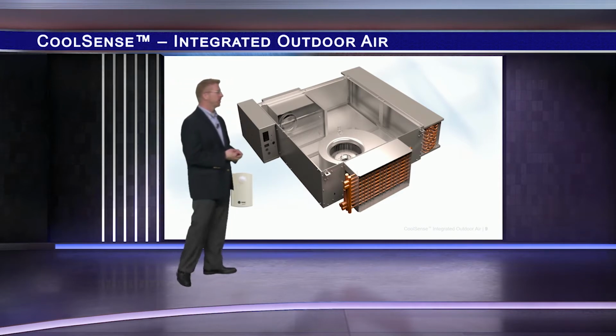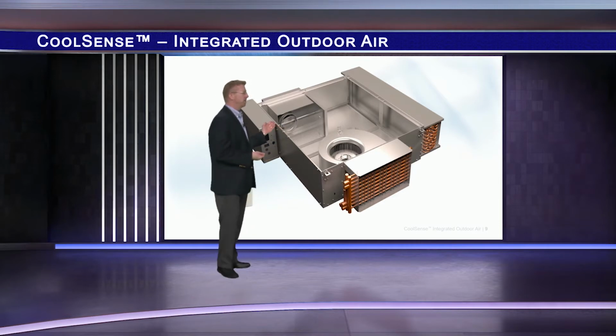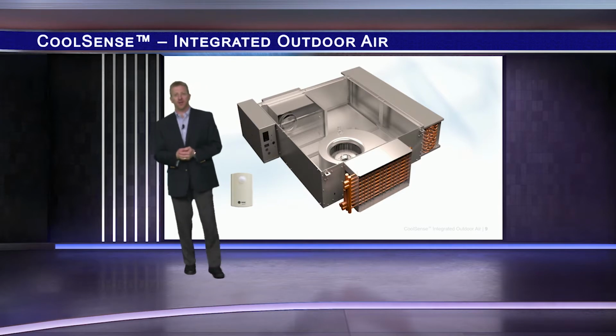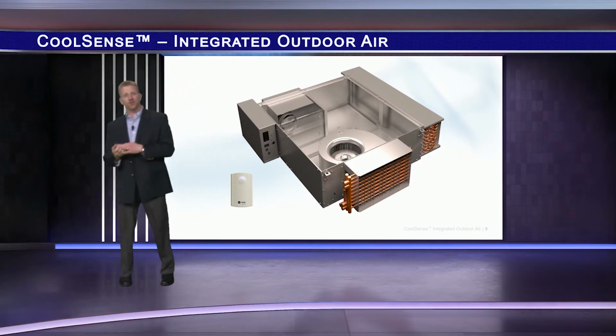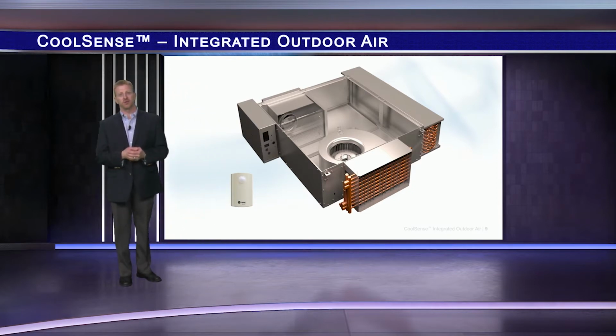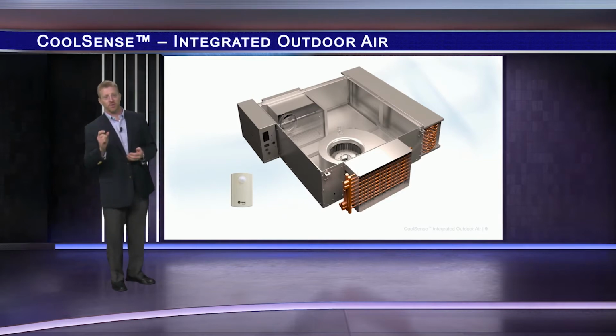Conditioned air delivered from the dedicated outdoor air unit enters the terminal unit through this air valve. The airflow measuring damper both measures and controls the outdoor air delivered to the zone. This is the same proven technology we've used in our conventional VAV terminals, but in this case, this valve is typically sized only for the minimum outdoor airflow required by code.